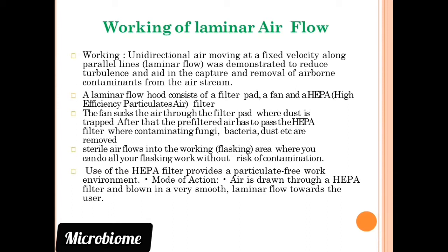Now what happens? The fan sucks the air through the filter pad. When dust is trapped, the pre-filtered air, that is primarily filtered air, has to pass through the HEPA filter, where contaminating fungi, bacteria, dust, etc. are removed. So basically, first air passes through the filter pad or primary filter, then it is collected by the blower or fan and passed through the HEPA filter, by which we get sterile air.